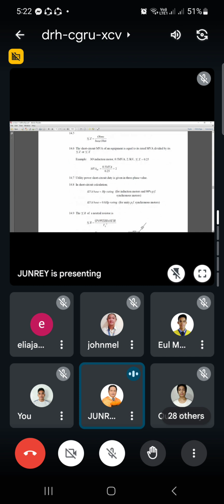Okay, next, the short circuit MVA of an equipment is equal to its rated MVA divided by its per unit Z or per unit X. For example, class, a three-phase induction motor, 0.5 MVA, 2.3 kilovolts, with per unit X of 0.25. So to solve the short circuit MVA, we divide: 0.5 MVA over 0.25, which equals 2.